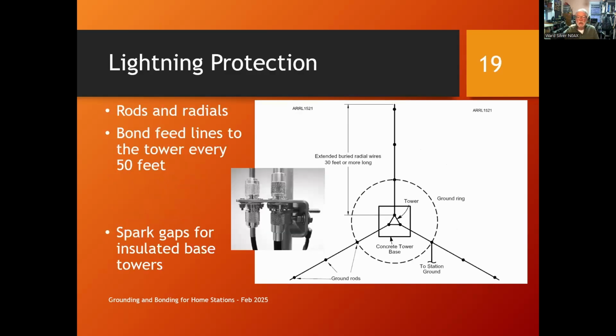If you've got a tower, and you've probably seen this in the handbook, you're looking down on a lattice tower like a Rohn 25 in a concrete tower base. The handbook and other references have told you for many years to take each leg, connect a galvanized clamp, and connect a copper ground wire from there over to a ground rod near the base, and do that for each leg.